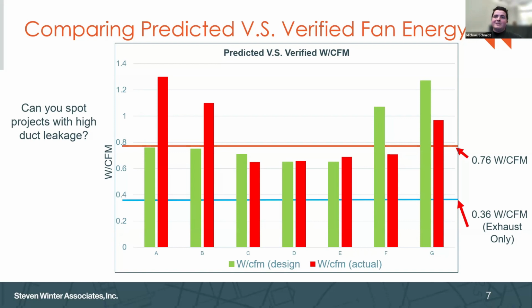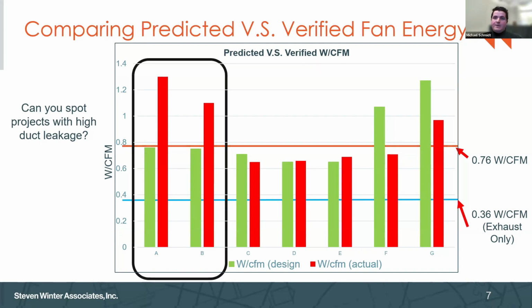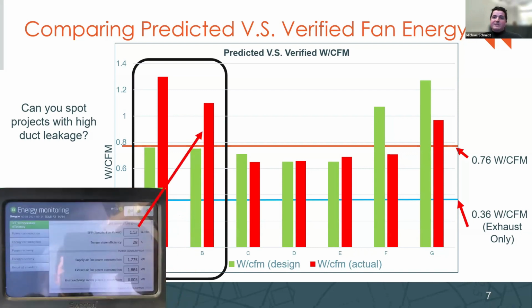Now, can we spot which projects have high duct leakage? Right, it's projects A and B. With significantly high duct leakage also comes higher fan wattage. Now, they're relatable, right? The metric is watts per CFM. So if we have higher watts per CFM, it's tagged along to a higher flow rate. It's sort of a double whammy to the energy model. It can significantly increase the energy consumption of that system. And here's just a graphic to show you what this might look like when we're verifying flow rates. Some units like the Swegon have a built-in controller with an energy monitoring screen that shows you in real time what the specific fan power is, here shown.